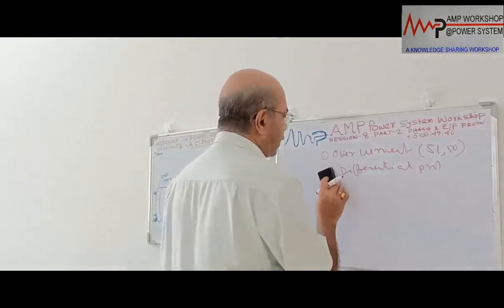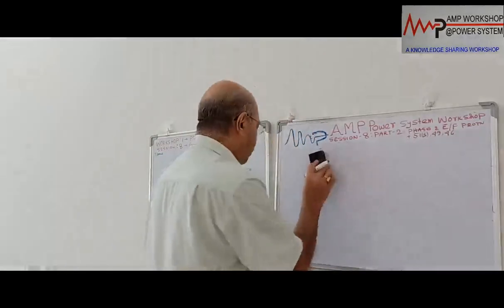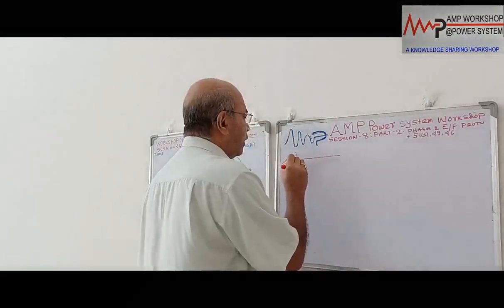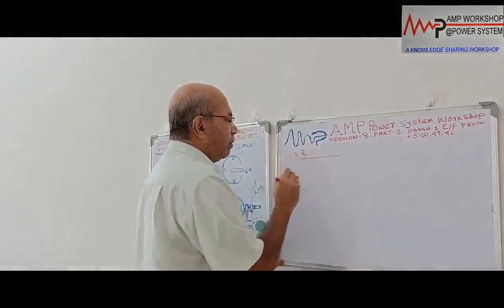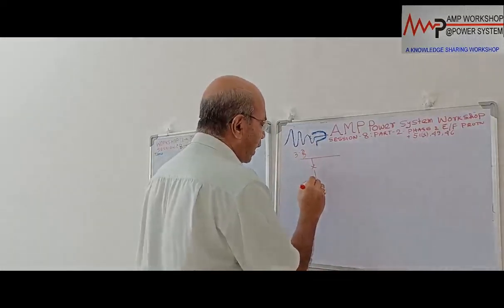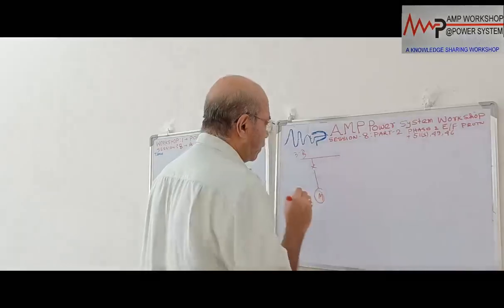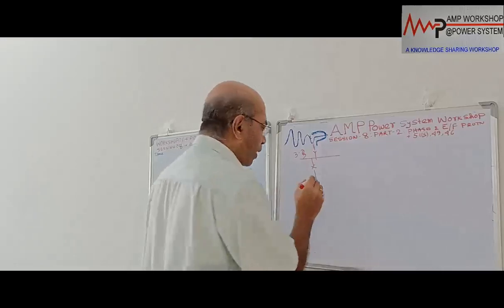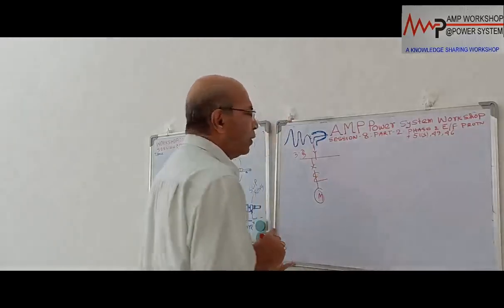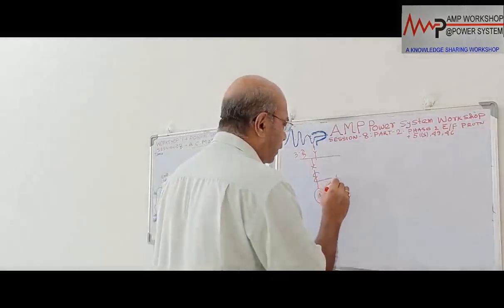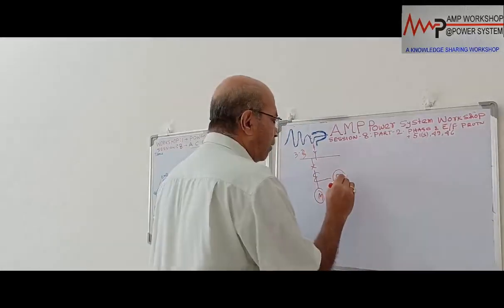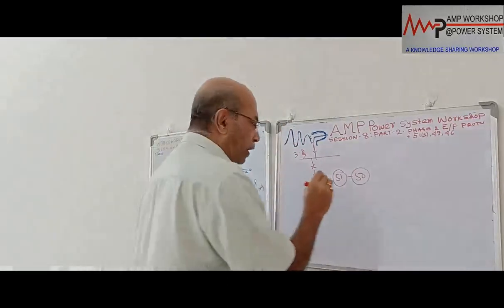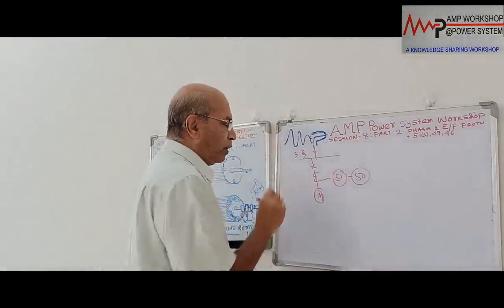Now how do we provide this protection? We are drawing a diagram. This is a switch gear. Suppose this is a 3.3 kV system, there is a breaker over here, and then the motor is connected over here. And there is an incomer over here. Now we provide a CT on this motor, and this CT we connect to an IDMT overcurrent relay, and we can connect an instantaneous overcurrent relay also. So an IDMT overcurrent relay is always provided for this type of protection.